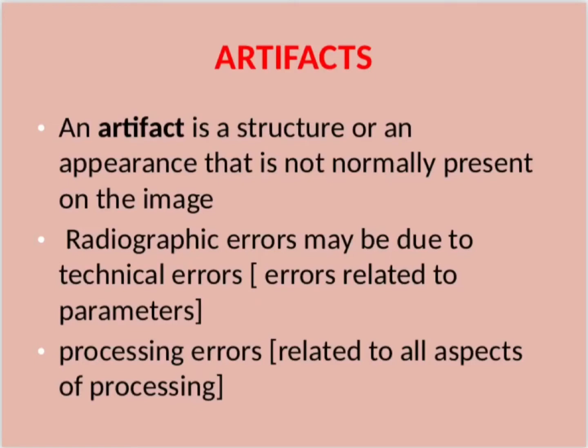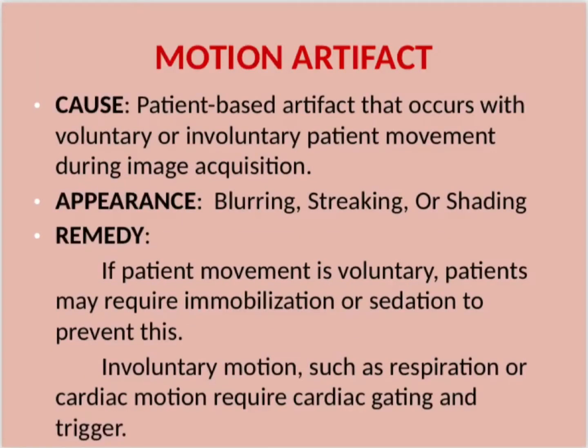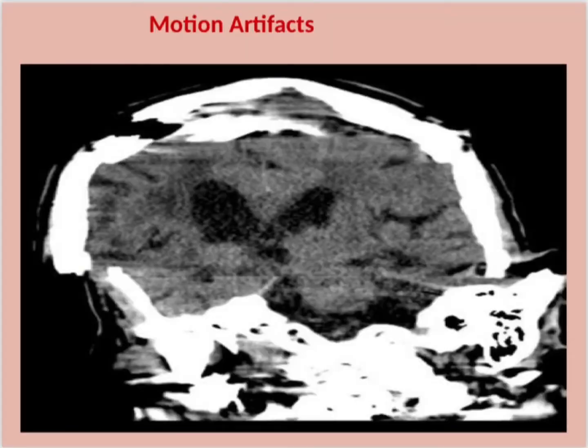Motion artifact is a patient-based artifact that occurs with voluntary or involuntary patient movement during image acquisition. Appearance includes blurring, streaking, or shading. Remedy: if patient movement is voluntary, patients may require immobilization or sedation. Involuntary motion such as respiration or cardiac motion requires cardiac gating and triggering.